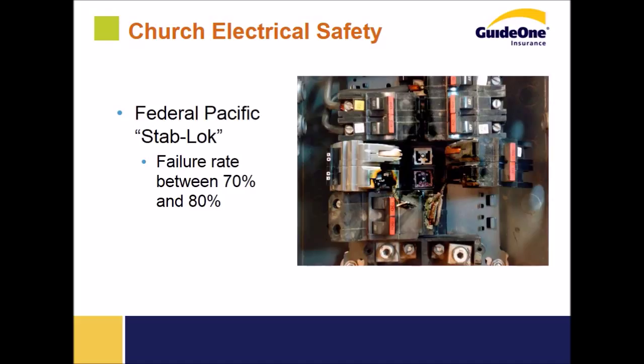The failure rate is somewhere between 70 and 80% when these breakers that appear to be in good condition are tested. So again, it's simply something that needs to be called to our attention. And we do have a pretty good history with our churches. If we're able to show them the problem, they usually are very willing to make the correction. And we've had many cases where they simply can't make the correction. We feel the risk is too great, and we'll take some underwriting action and cancel that policy.